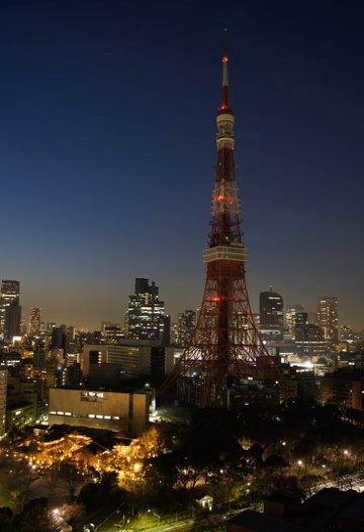Power failures are particularly critical at sites where the environment and public safety are at risk. Institutions such as hospitals, sewage treatment plants, mines, shelters and the like will usually have backup power sources such as standby generators, which will automatically start up when electrical power is lost. Other critical systems, such as telecommunication, are also required to have emergency power. The battery room of a telephone exchange usually has arrays of lead-acid batteries for backup and also a socket for connecting a generator during extended periods of outage.